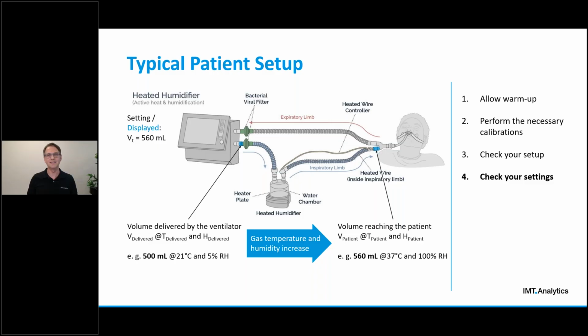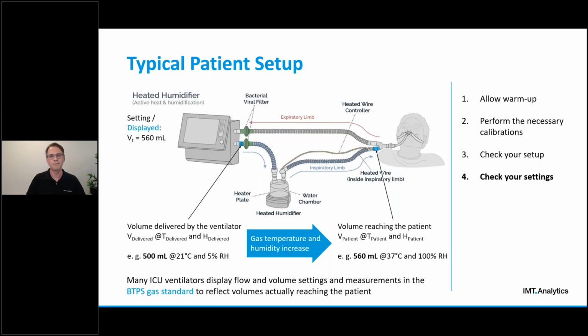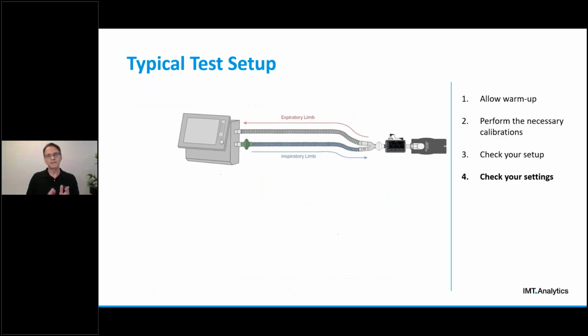I'm pretty sure that many of you have heard this term because most ICU ventilators actually display settings and measurements on their device in the BTPS gas standard to reflect the volumes that are actually reaching the patient. So what's the issue here? Well, when we test such a ventilator with a gas flow analyzer, the test setup typically looks like this. So we have the circuit system, Y-piece, our analyzer, and then a test lung.